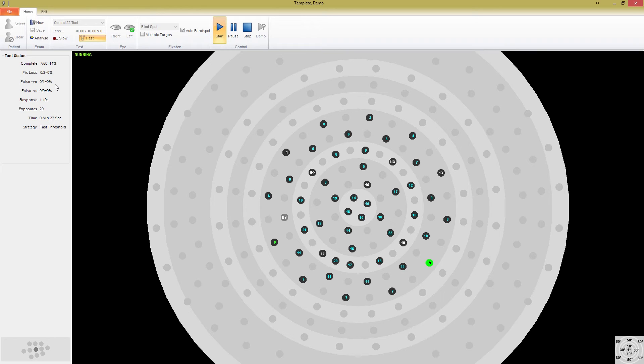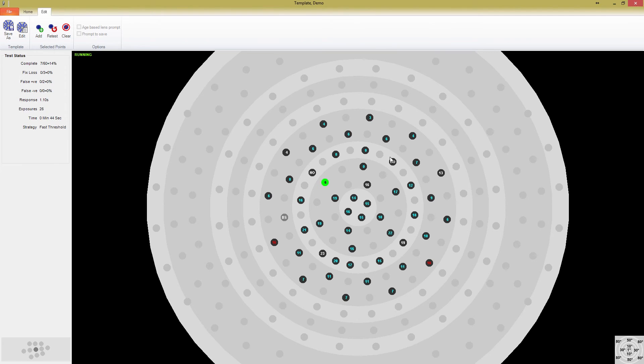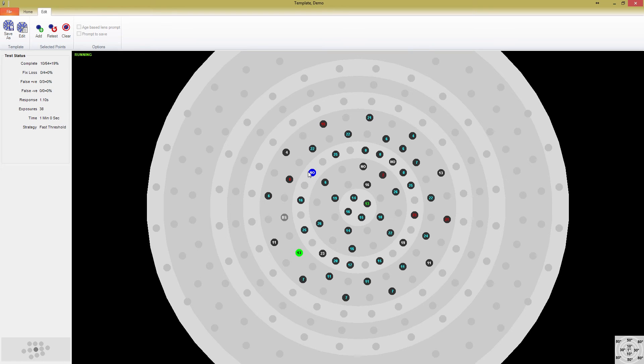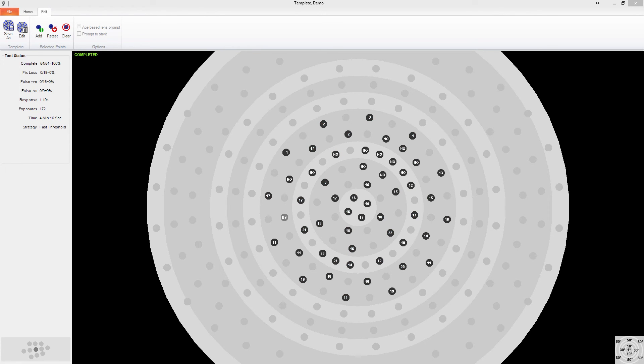Now is where things get a little more fun. While the test is running, you still have a lot of control. If you click on the edit tab in the top left, you'll see the option to add and retest points. If we take a look at this test, which is continued to run, we see what looks like a defect. If you want to explore the surrounding area to see the extent of the defect, all you have to do is click on the points you're interested in, and press add. You can see that these points are now ready to be tested in real time. Similarly, you may find a defect that looks suspicious and wonder if it's just a patient error. No problem, just select the point and press retest. Medmont Studio will incorporate that point back into its testing program. These options to add and retest are also available at the end of the test without restarting it. Just add the points you're interested in, and press the start button to complete the test. You'll notice that the software will include a couple of points from outside your selected points to give the illusion that this test is random.